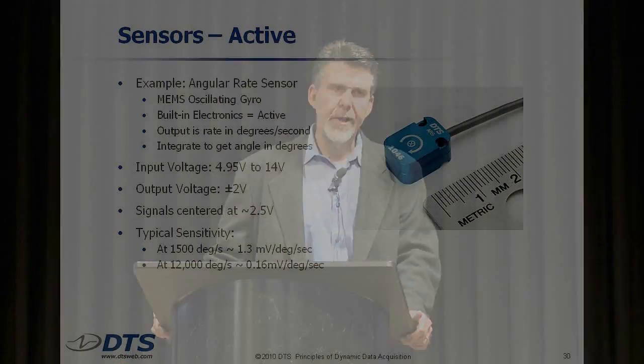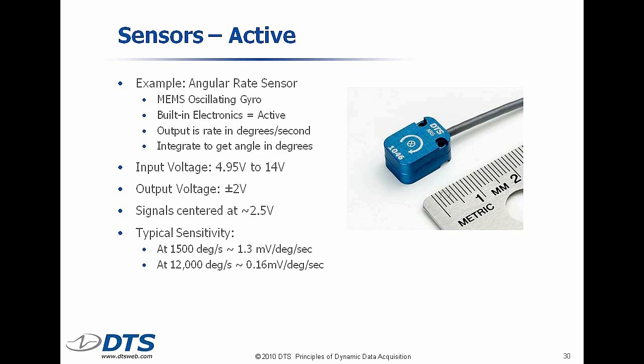Now, a different class of sensor is what we call active. Now, these are not bridge transducers, and they do not have a Wheatstone bridge. It's important because if you're setting up a data acquisition system to work with a sensor, you need to know what the fundamental technology of the sensor is. If it's a bridge, okay, they're all pretty much similar. There might be some nuances, you know, like what's the bridge resistance and how much output does it have, but they're all basically the same. With active devices, they typically have some kind of sensing technology inside, as well as a tiny circuit that amplifies the signal. It might regulate the power supply. It might do all sorts of stuff in there that you know nothing about. The bottom line is that an active transducer needs to be treated differently than a passive transducer, which is what we call bridges. And I'll talk about that in a little more detail in a minute.